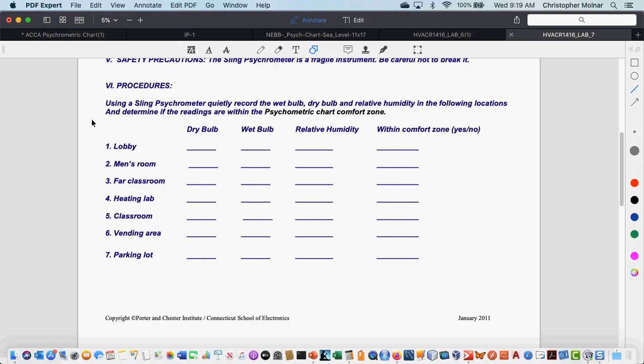For those who do not have the psychrometer, to get a wet bulb temperature, you take your meter—it has a temperature probe on it. Put a small piece of paper towel that's damp, not dripping water, just damp, over the end of that meter, and you can take wet bulb temperature. Put it on there tight enough where you can move it around in the air to get some air patterns across it, and just give it 5 minutes and you can take a wet bulb temperature.